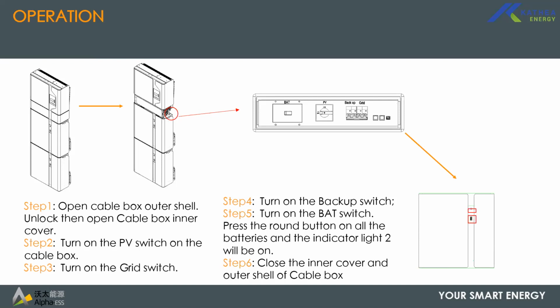So for operation, most of the settings come pre-configured, but a few settings have to be set to the specifics of your operation. So the power on procedure, when everything is done and checks have been done to see that everything is wired and the inverter is properly grounded, you would need to open that small strip cover just under the inverter to access the control box. Inside the control box, you get your grid, backup, PV, and battery breakers.